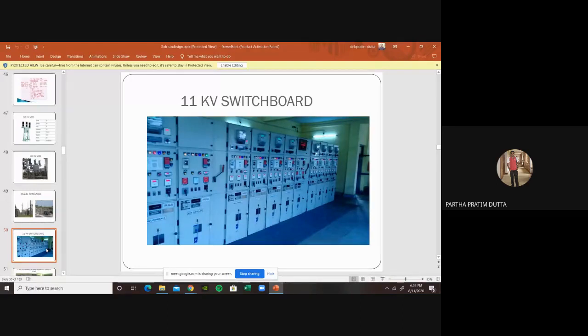Previously we had the oil circuit breaker. It was very bulky and shabby, but we have already replaced it with a very slick and usable VCB, vacuum switchgear. This portion is called the make-break switch. Any making and breaking happens in this lower portion of the switchboard or switchgear. In the middle portion, the bus bar, all the meters and the control system are placed, and the top portion holds the meters. All of that is looked after through this.